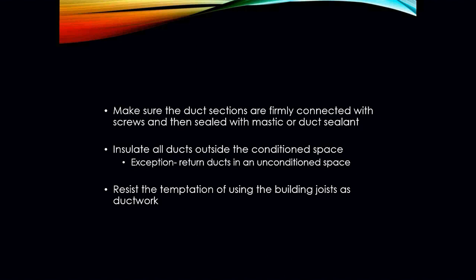We want to make sure that the duct sections are firmly connected with screws, slips, and drives, and make sure that they are sealed with mastic or duct sealant. We are also going to insulate all of our ducts that are outside the conditioned space. What do we mean by the outside of the conditioned space?